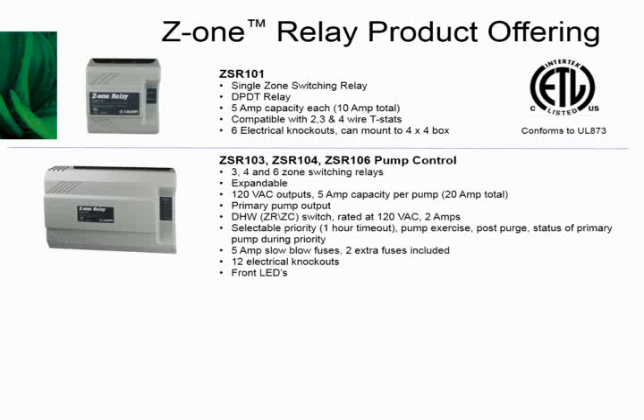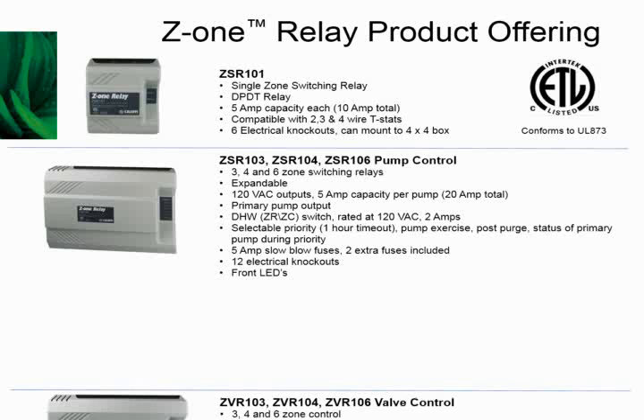There's a post-purge option, and then also something we call the status of the primary pump during priority. So what that allows us to do is you can decide whether you want a primary pump to run during the priority mode. We'll show some of the schematics with that later too. 5 amp slow blow fuses, 2 extra fuses under the cover. This one has 12 electrical knockouts and the front LEDs for easy diagnostics.